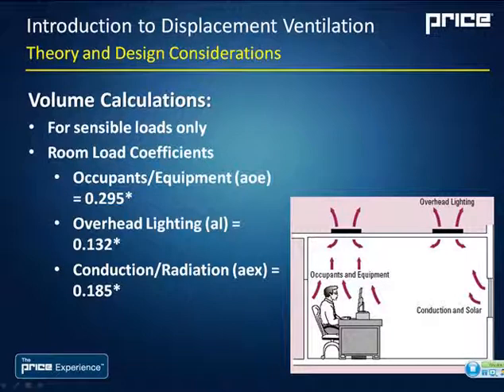So what we're left with is around 30% of the occupant and equipment load falling in the occupied zone, about 13% of overhead lighting falling into the occupied zone, and about 19% of the conduction and radiation through the envelope and through windows falling into the occupied zone. So it's a significant reduction from the standard case where we would mix all of the heat load into the room.